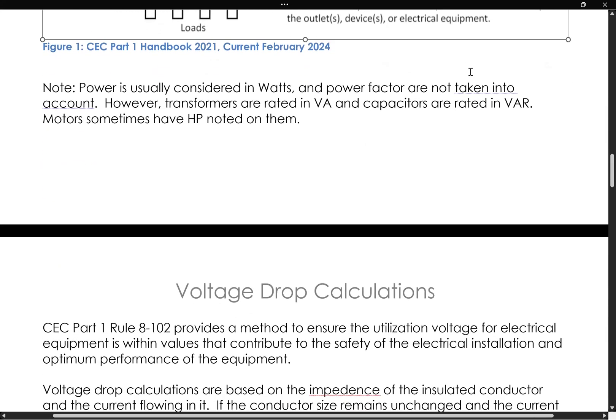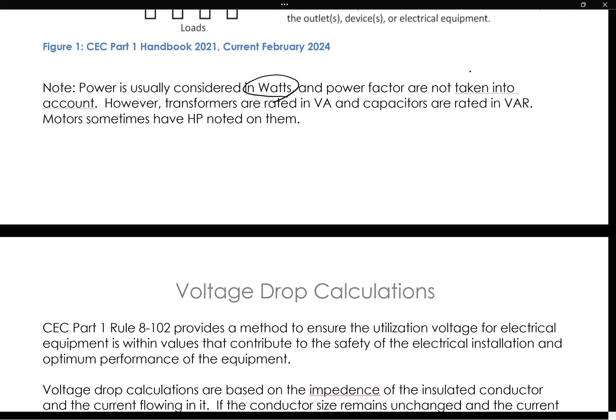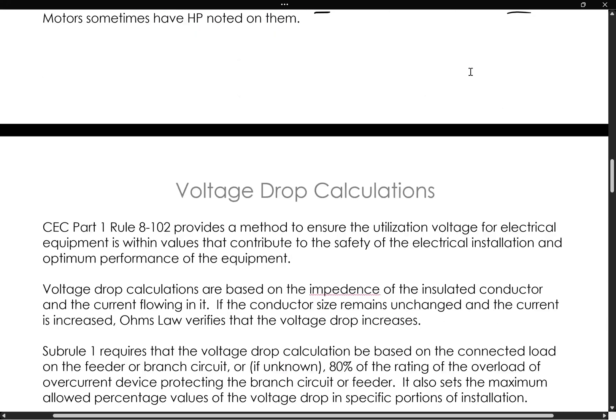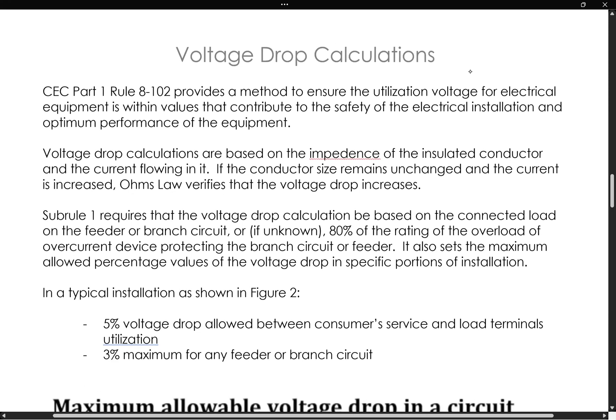It's worthwhile to note that power is usually considered in watts for these calculations, and we don't take into account the power factor for these calculations. We get the system up and running before you take a look at the power factor. Don't forget, though, that some equipment is not going to show watts on the nameplate. You're going to see volt amps for transformers, you're going to see volt amps reactive for capacitors. Motors sometimes are even rated with horsepower on them, which you can readily convert from.